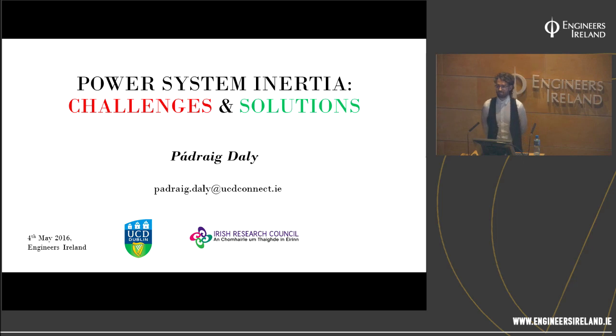We have developed a demonstration plant in the old power station plant in Offaly in conjunction with EirGrid, using flywheels and batteries to provide system services. And what they will do under the DS3 is they will pay an uplift or a multiplier on the fast frequency response payment if you can get in before the 2 seconds. So fast frequency response is from 2 seconds out to 5 seconds, and then primary operating reserve is 5 seconds out, and so on. So if you can get in in half a second, they will pay you more. So they do see that there's a value, even though it's not actually synchronous inertial response.